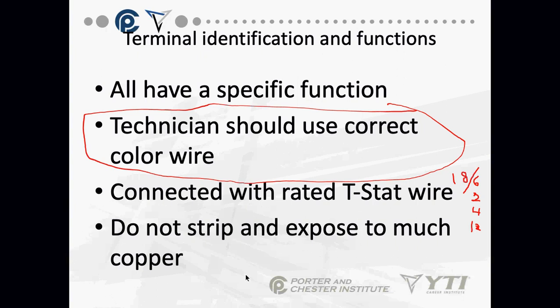When you're stripping thermostat wire back, getting rid of the insulation, don't strip too far back. Just strip the amount of insulation off the wire that you need to get under the screws. It's very easy to have a short circuit at the thermostat. You are wired to the sub base of the thermostat, you put the thermostat front on, and all of a sudden you have way too much wire exposed. So don't strip and expose too much copper.